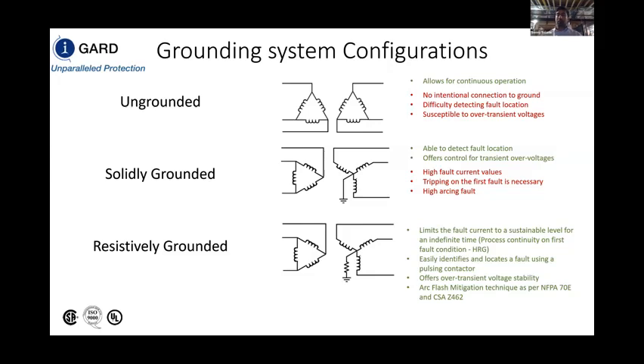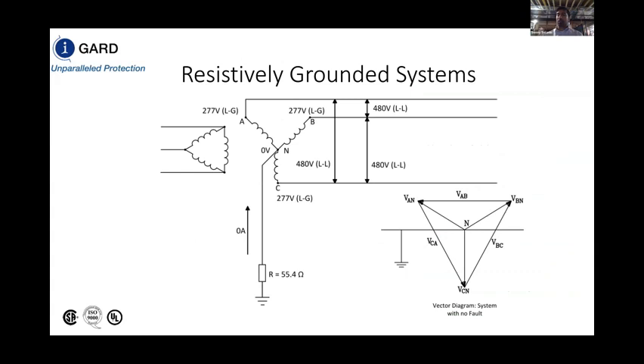The in-between ground between ungrounded and solidly grounded systems is a resistance grounded system. In a resistance grounded system, we're essentially limiting the fault current to a specific value in an effort to not allow the arc enough energy for it to build up to a higher level of power. In addition to that, we size the resistor in accordance with the charging current coming from the capacitance in the system such that we can control the transient overvoltage condition. And we can also easily locate faults in this system since the technology is very similar as with the solidly grounded system. And also we have a pulsing feature on our resistors, which can help in locating faults. So it's now practically used everywhere, where data centers, hospitals, and other process industries which can't tolerate a fault are utilizing this type of technology.